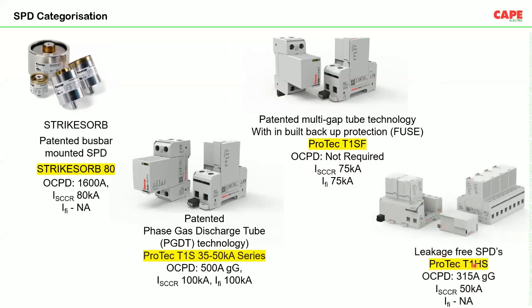Another device, ProTec T1HS. Here, the device requires a 315 amps backup fuse. Its short circuit withstanding capacity is 50 kiloampere. Follow current is not applicable. So why am I showing these parameters? All these SPDs are type 1 SPD, but they are also tested for type 2 parameters. So we can call it a type 1 plus 2 SPD, but basically the main categorization is type 1 SPD. All these are tested for a 25 kiloampere impulse current. The current parameters we will discuss in the next upcoming seminar. So all these SPDs are tested for 25 kiloampere.